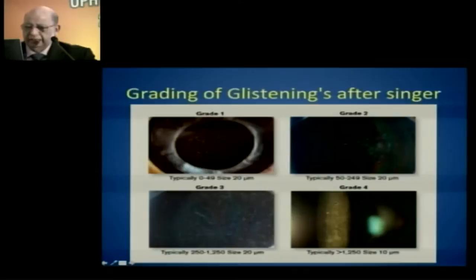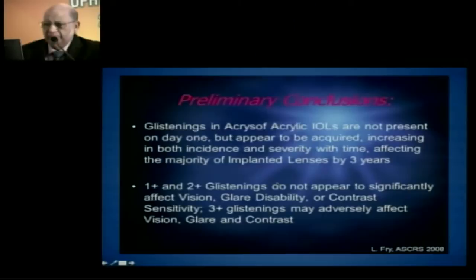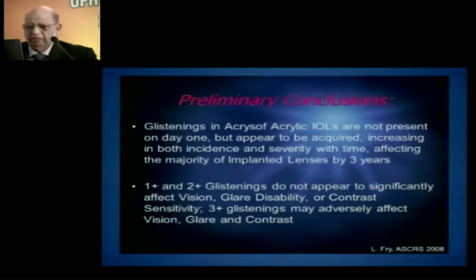The grading of glistening, after Singer who did a great deal of work on it, goes from Grade 1 — hardly any — to Grade 2, Grade 3 at almost 20 microns in size, up to Grade 4 where it becomes extremely obvious. Though glistenings don't seem present at day one, they progressively increase and cause glare and contrast sensitivity problems.